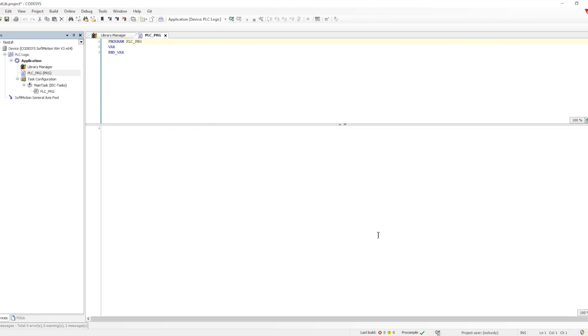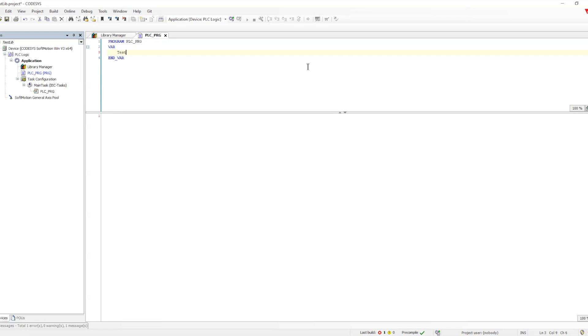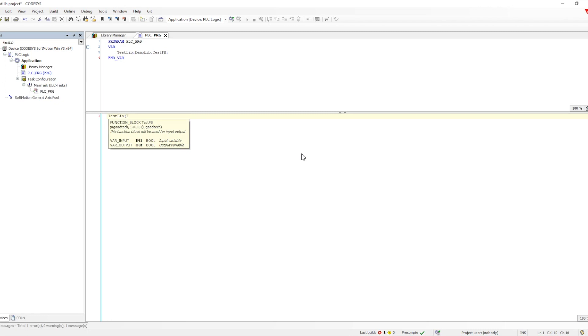Now that the function block is there, I want to instantiate it into my project. We need to define an instance name first — let me define it as 'testlib'. Then we use the namespace of the library, which we defined as 'demo lib'. When I type the namespace followed by a dot, it shows all available function blocks. Once the instance is created, it's the normal process for defining and using any function block in logic.